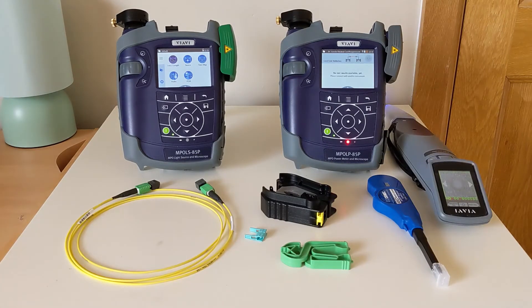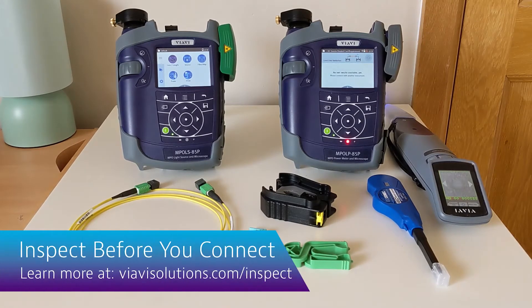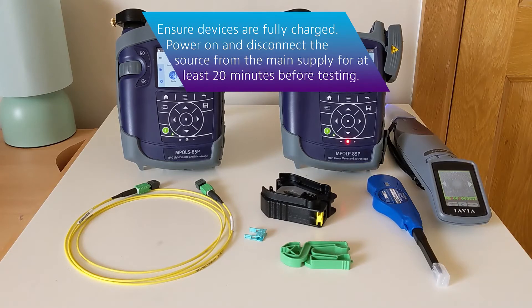The first step in referencing is to ensure that all of your test cords and the ports on your testers are clean. For this we'll emphasize the inspect before you connect approach using appropriate viewing scopes and cleaning materials. Make sure you charge your testers ahead of time, but ensure your source unit is powered on but disconnected from power for at least 20 minutes before you begin.